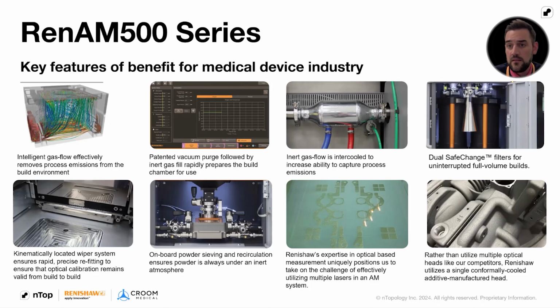It helps us maintain proper metallurgical integrity of the welding process and keeps the optical window clean to ensure good laser quality. Moreover, that gas flow is recirculated in the system through an intercooler, which helps us maintain not only gas flow temperature, but helps exhaust condensate, spatter, and things of that nature throughout the welding process. But maybe even more importantly, it helps maintain optical control and stability of the optical module and laser systems, i.e. things like scan field, power mapping, beam profile, and focus of the laser, for example.